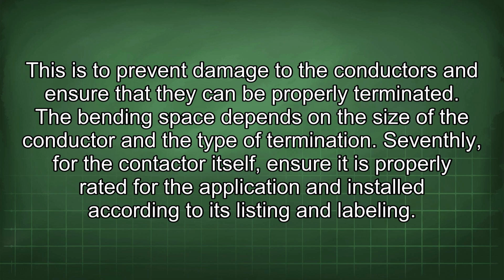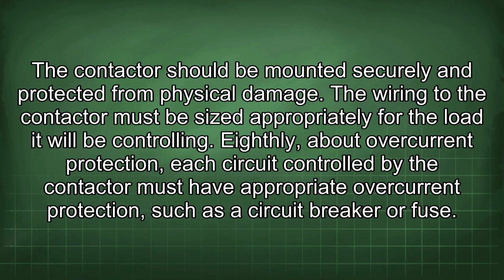Seventhly, for the contactor itself, ensure it is properly rated for the application and installed according to its listing and labeling. The contactor should be mounted securely and protected from physical damage. The wiring to the contactor must be sized appropriately for the load it will be controlling.